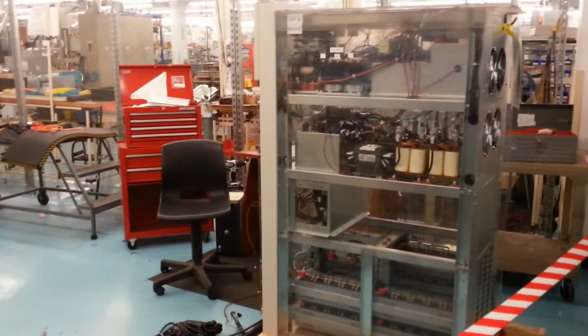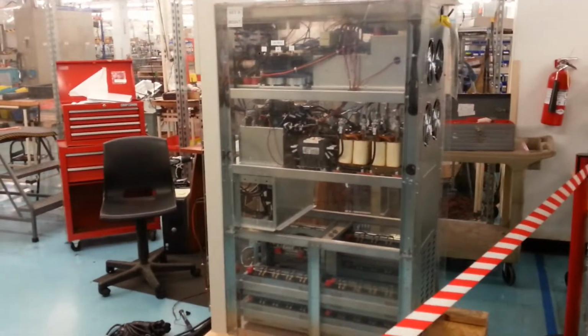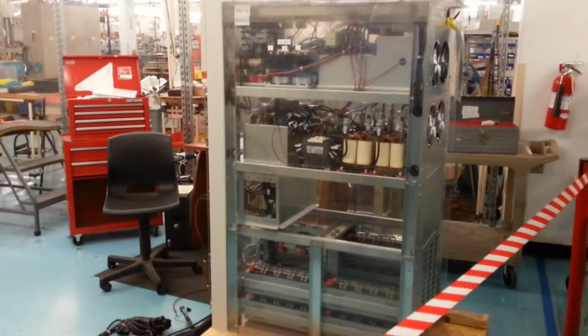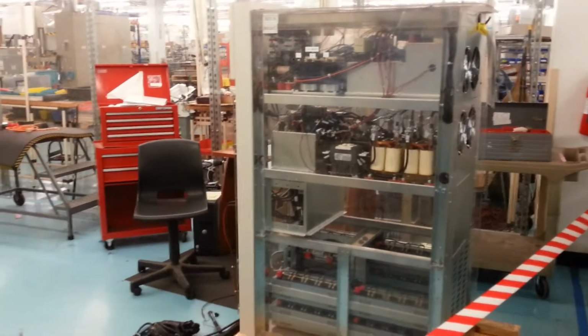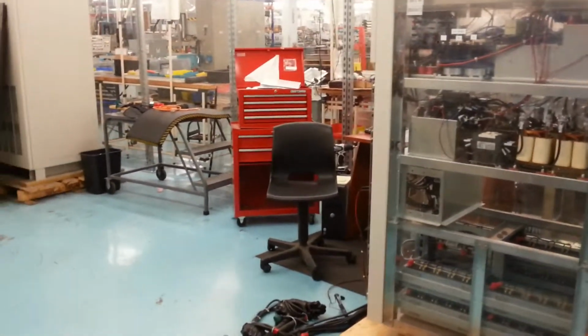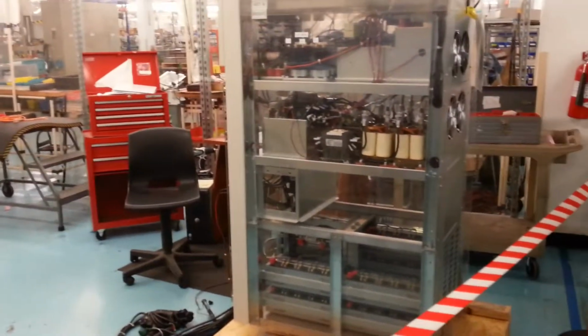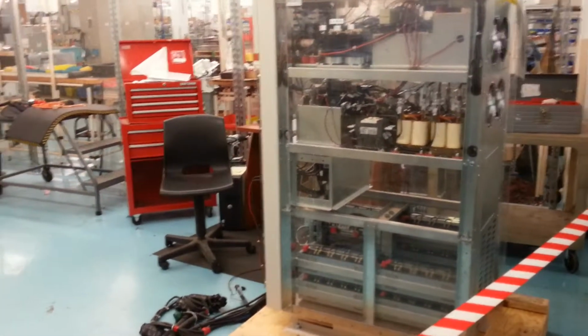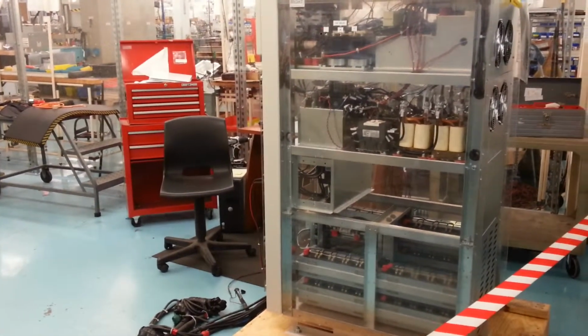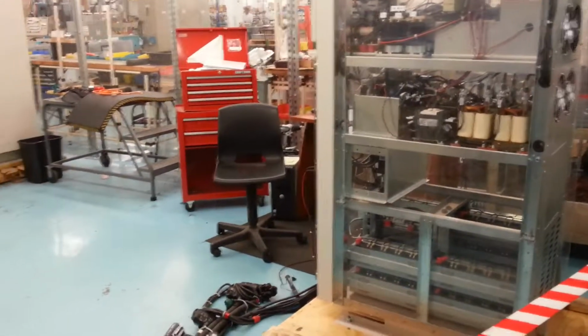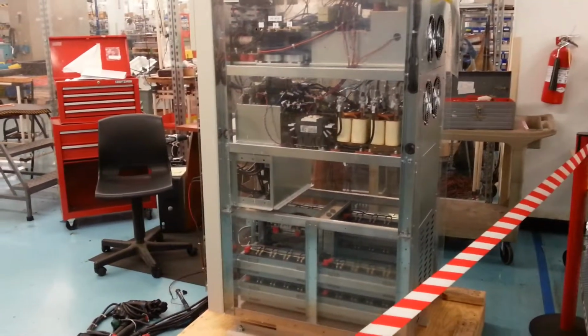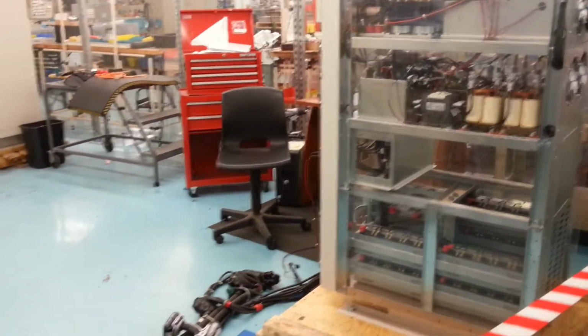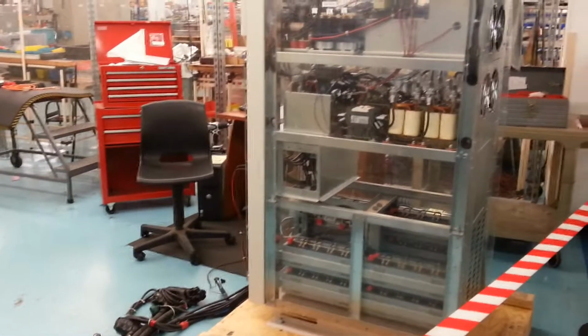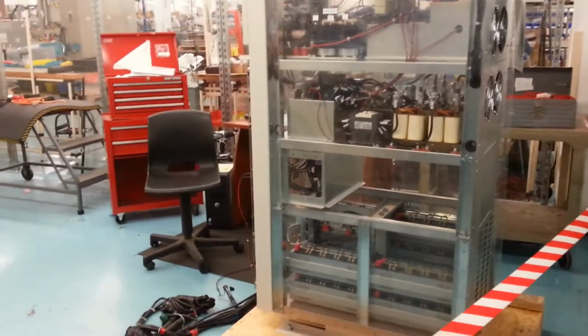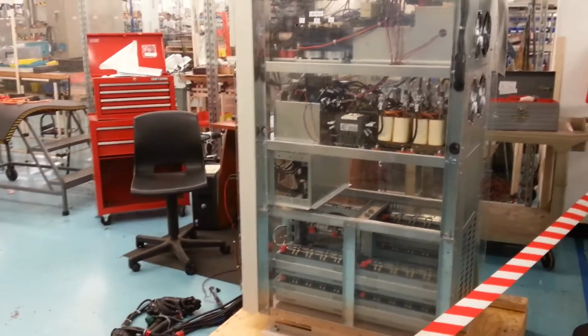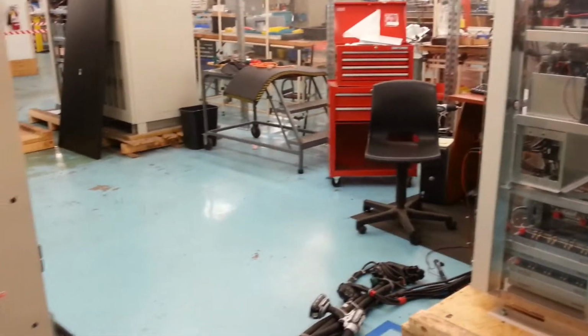Most of the time these days, generators will synchronize in less than 15 seconds. Spin up to speed, sync the frequency, and transfer online. Which then, once it comes online, UPS sees power came back, it transfers back online, takes the grid from the generator. Or we have customers that have the flywheel. You know, we have a flywheel, what size of flywheel to give the customer about 12 to 15 seconds of runtime. Because that's about all that flywheel is going to give you anyways. Same thing. 15 seconds. So several minutes.